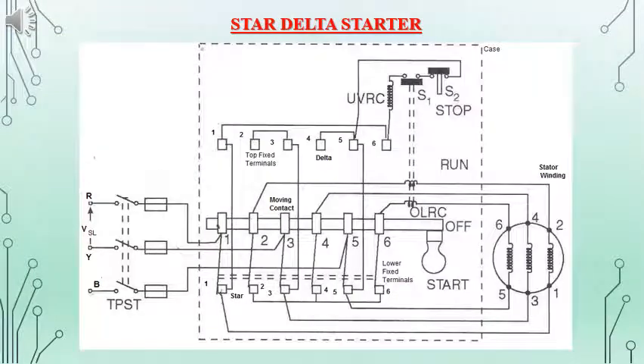Here we have the diagram given for the star delta starter. It is almost the same as that of the auto transformer starter. By the arrangement given, in the star condition the stator winding will be connected in star, and for the running condition the stator winding will be connected in delta. Along with the starter, we have the protective mechanisms for under voltage and overload.